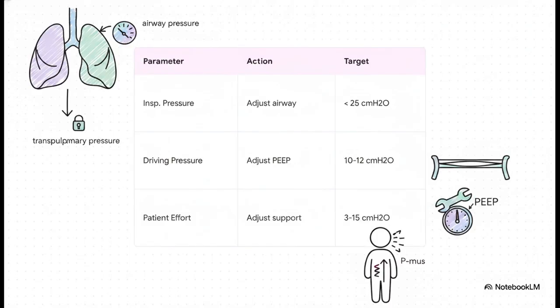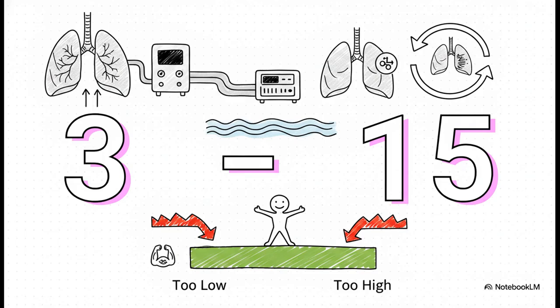So what does this look like in practice? Well, the automated system translates all those physiological parameters into hard, actionable targets. It constantly adjusts the applied airway pressure to keep the inspiratory transpulmonary pressure safely below 20 to 25 centimeters of water. It constantly tweaks PEEP to keep the driving pressure in a really tight 10 to 12 centimeter limit to prevent lung injury. And then there is the patient effort, or P-mus. 3 to 15 centimeters of water.